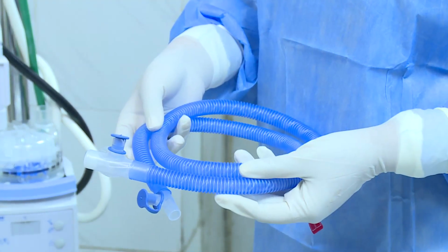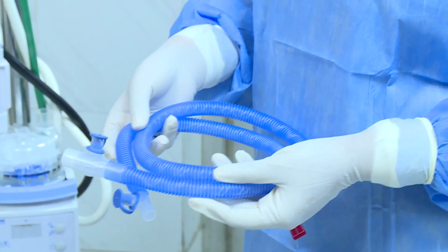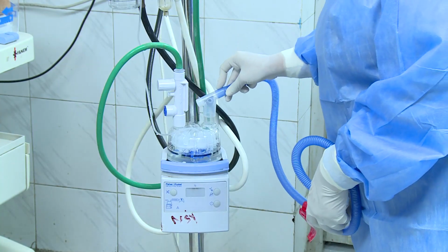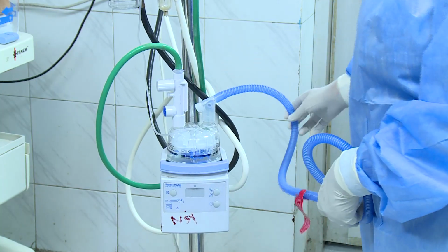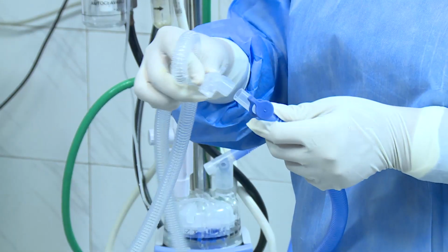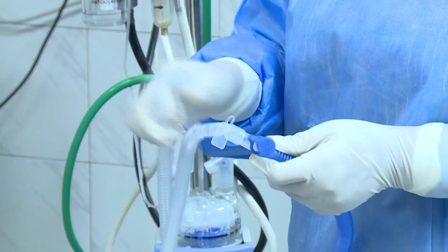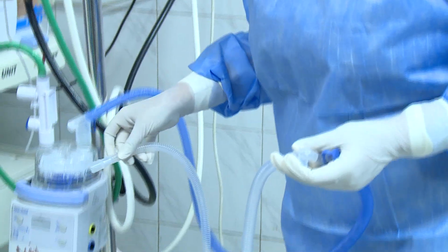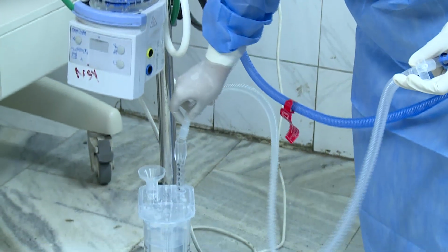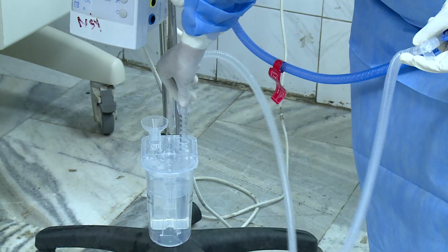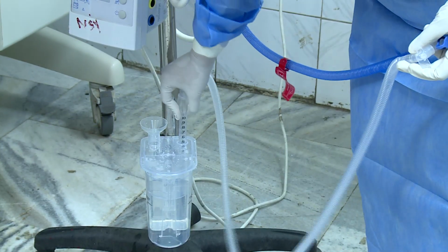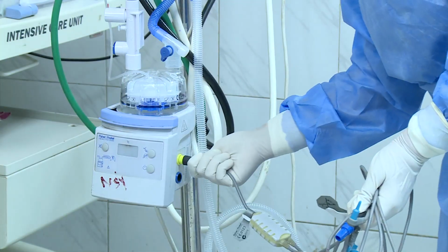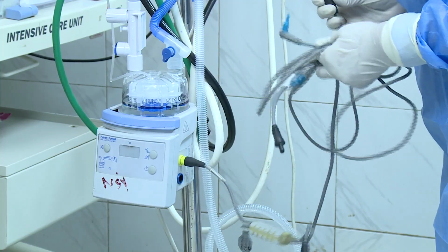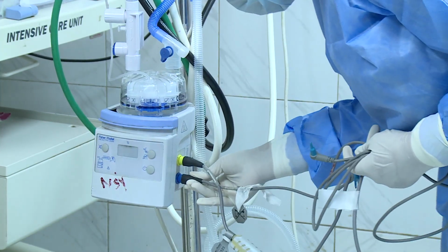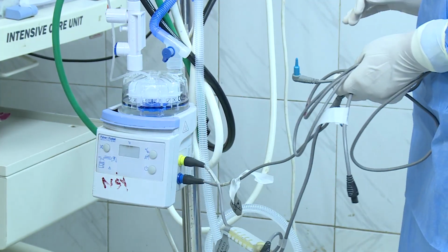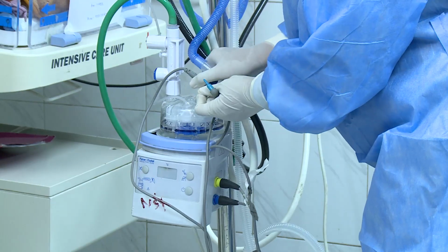The blue color signifies the inspiratory tubing, one end of which is connected to the water chamber and the other end is locked with the white expiratory limb. The other end of the expiratory limb is connected to the bubble chamber. Fix the heater wire and the temperature probe to the appropriate color-coded slots on the humidifier and the inspiratory circuit.